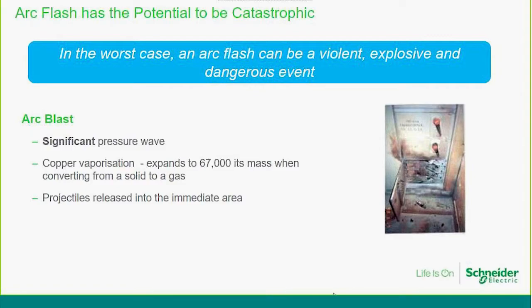And you're looking at an LV problem. Somebody was actually changing some fuse switches inside an LV panel. I think they changed the fuses, and when they reinserted the fuses back into the circuit, there was a problem, and it blew the door open. And clearly you can see by the dissipation of the energy how the switchboard has been affected by that. So we do face this every day when we're operating and maintaining electrical equipment.